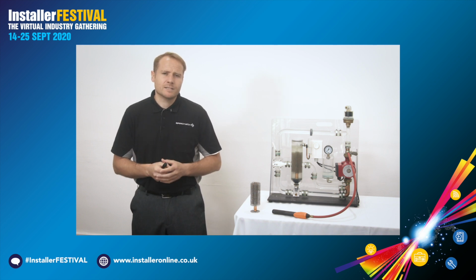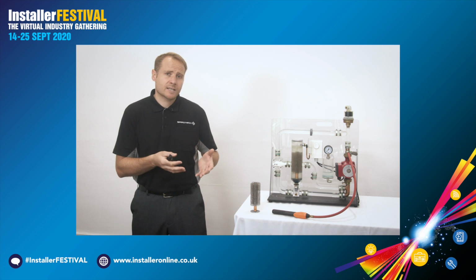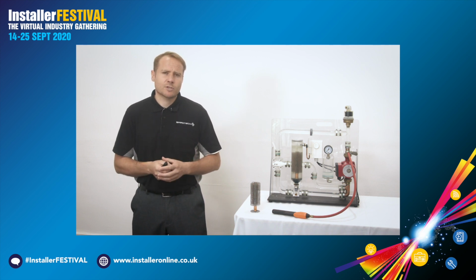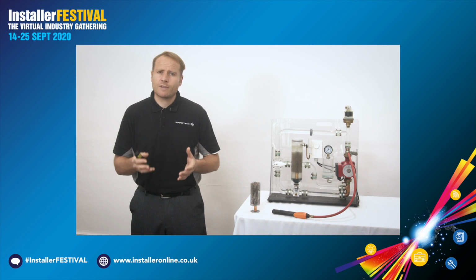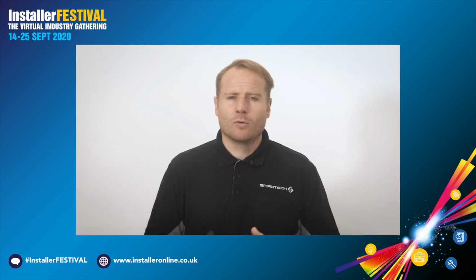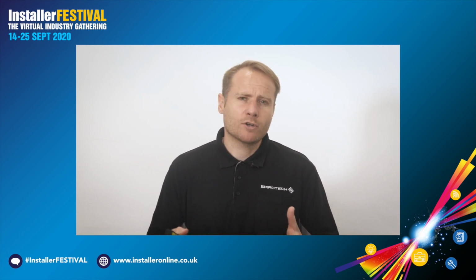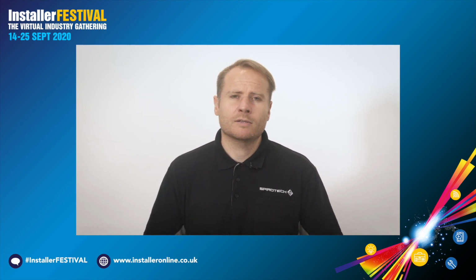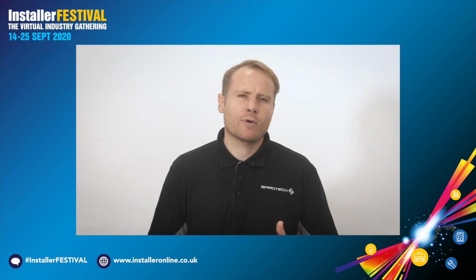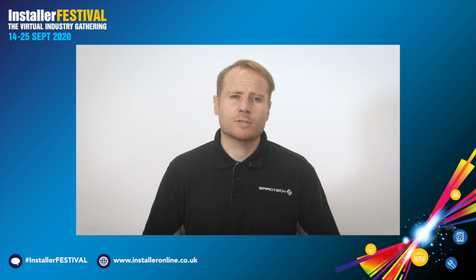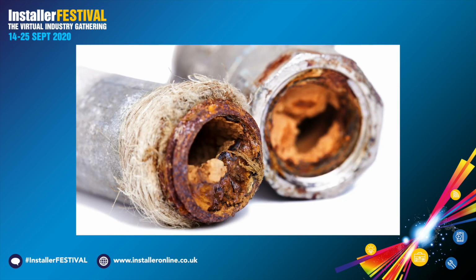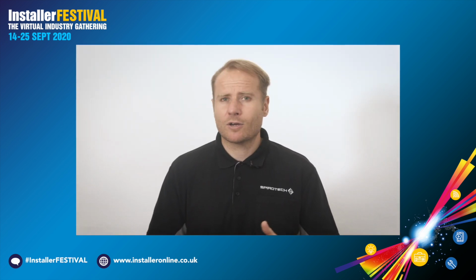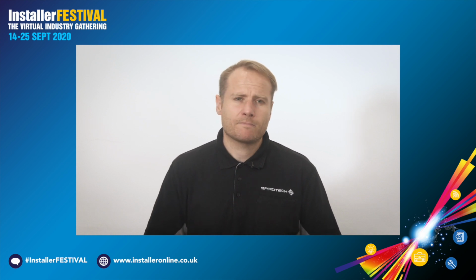One of water's abilities is to absorb gases. Now, the amount of gas that water will absorb, in this case air, is dependent on temperature, but it's also dependent on the partial pressure of that gas in contact with water. We know that air contains oxygen, and it's the dissolved oxygen within the water from the absorbed air that promotes corrosion. This electrochemical reaction is the breaking down of the system components. This produces the rust and magnetite that we see in systems, and we know that this can have a costly effect. Higher running costs, frequent failures. So dissolved oxygen will have a detrimental effect on the system.